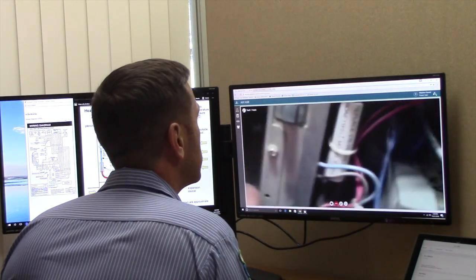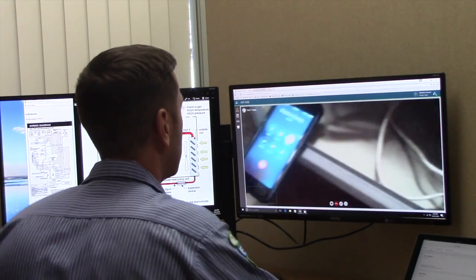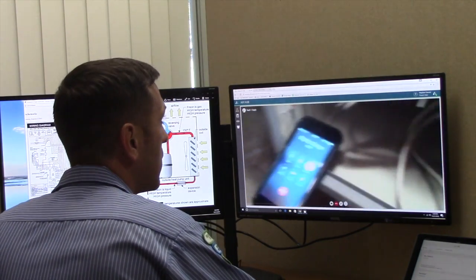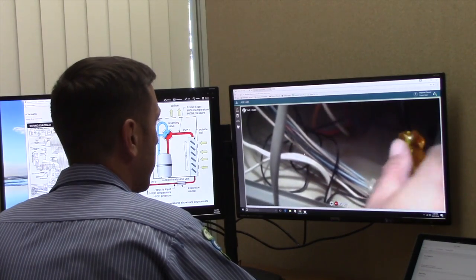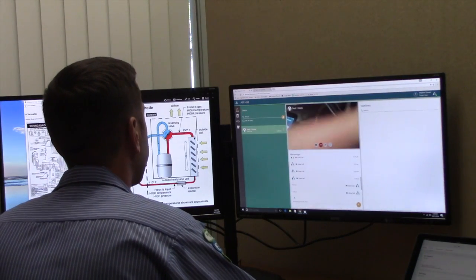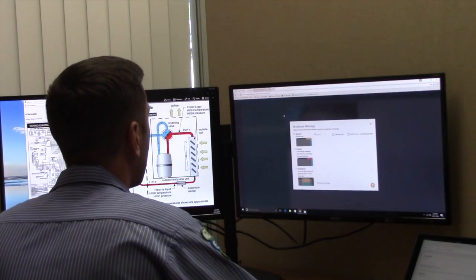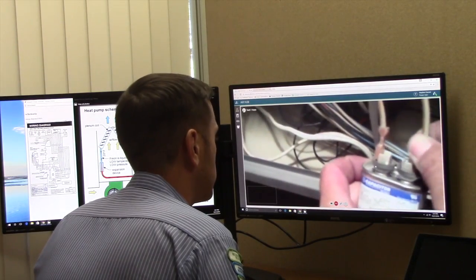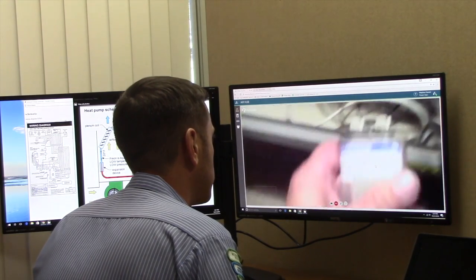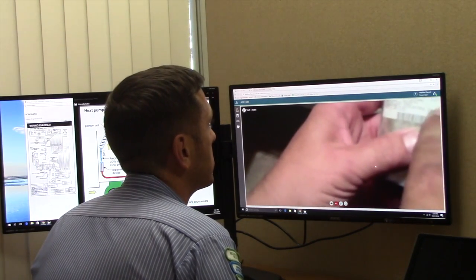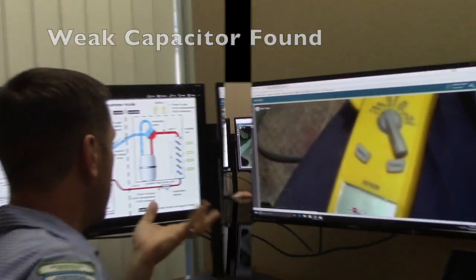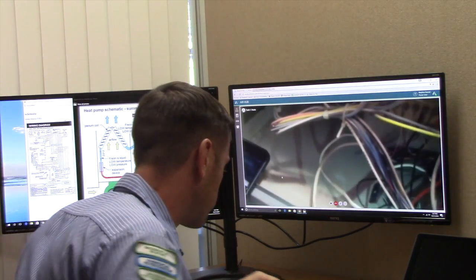I'm actually working on two furnaces. They're about 8 years old. He's doing the $49 special. Okay. And what I'm doing right now is just pulling the capacitor out so that I can test it. You see the 10 UF? You see the 8.21? Yeah, so I'm gonna go through this tune-up with you by the numbers.